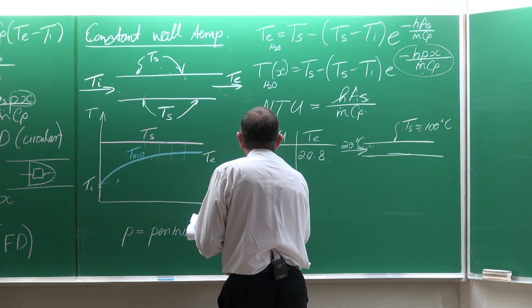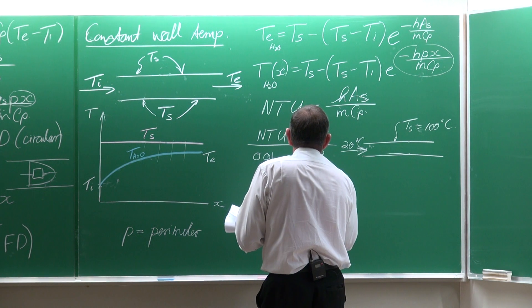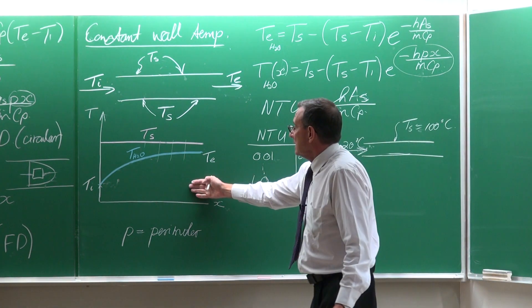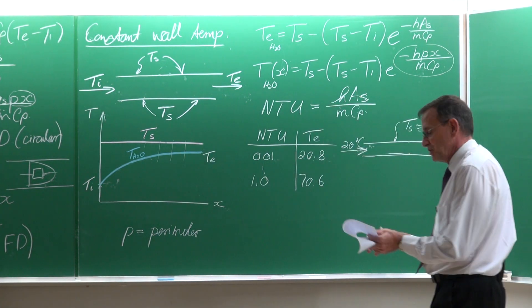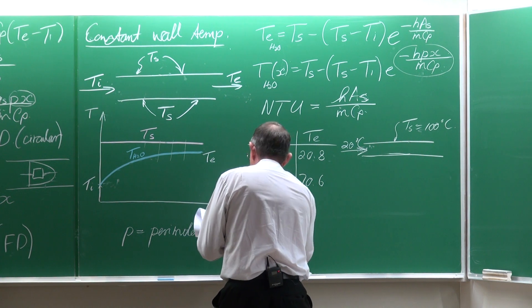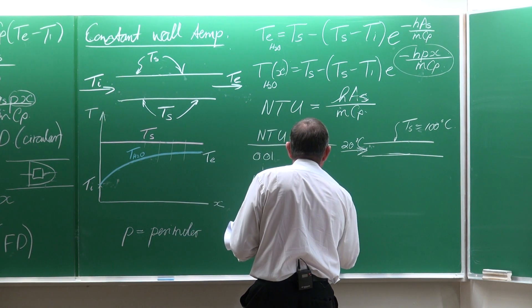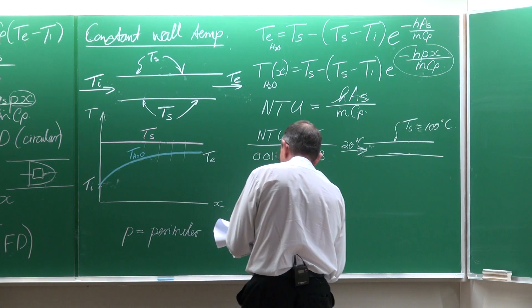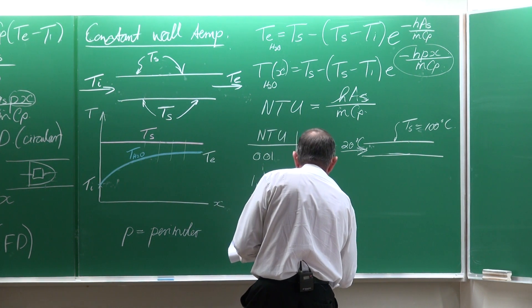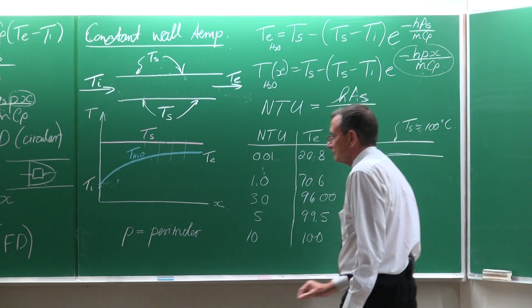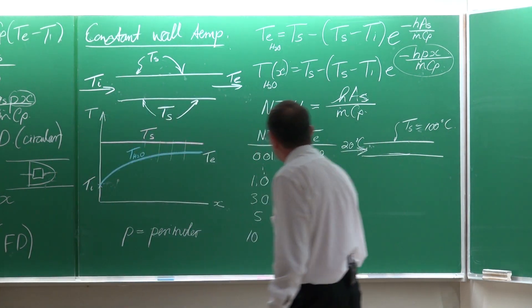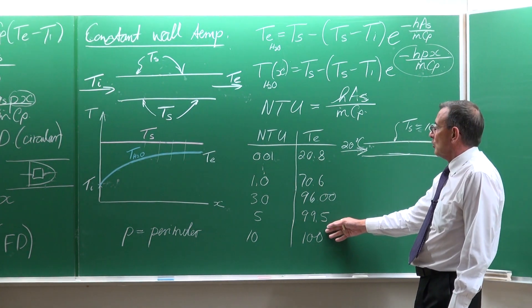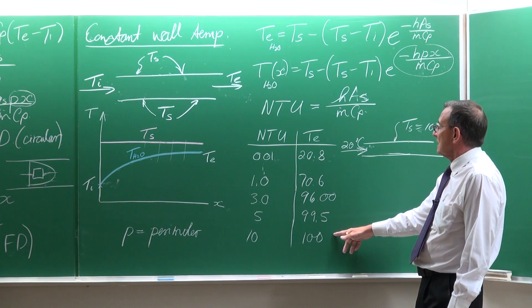So if you want heat transfer and the NTUs are low, you're going to get very little heat transfer and your heat exchanger is not going to be effective. If the NTUs become 1, the outlet temperature increases to 70.6 — a 50 degree rise. If it becomes 3, the temperature is 96. If it is 5, it is 99.5. And if it is 10, it is 100 degrees.